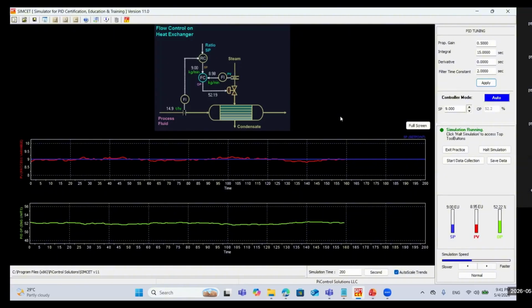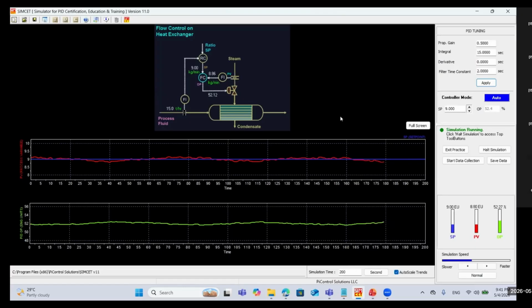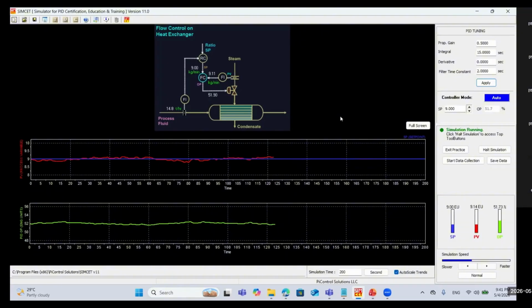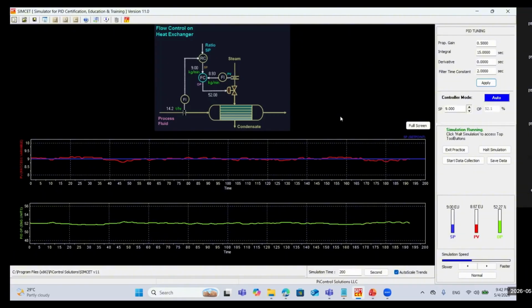Differentiating between poor tuning and mechanical issues. Okay, so as I mentioned, if it is a mechanical issue, tuning will not solve it. You will not see an effect. If the valve is having stiction, even if you change the tuning parameters, the valve will not have a good performance. Maybe in some rare cases it will have a good performance, but if plant load changes or some upstream condition changes, then the same issue will reoccur.